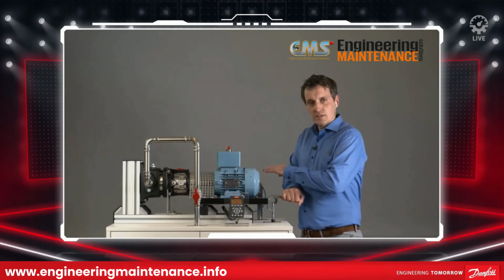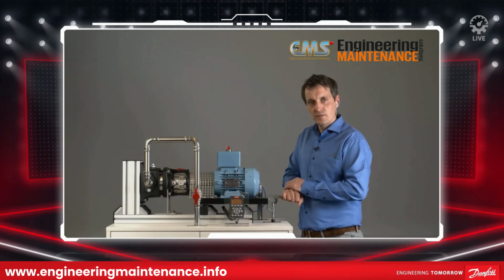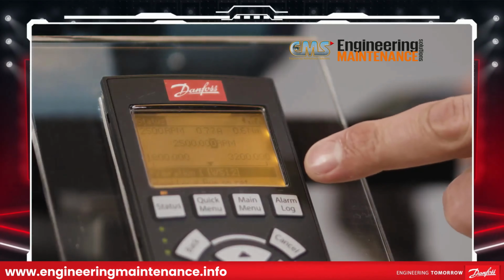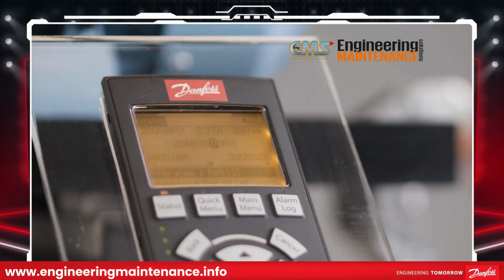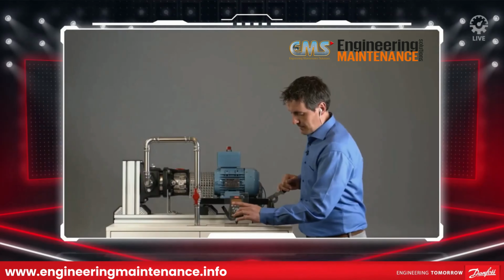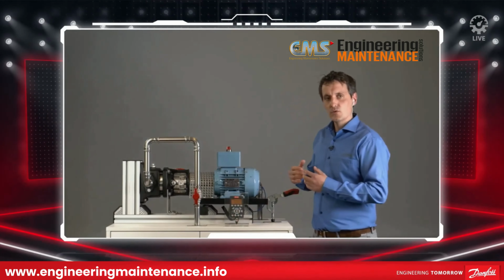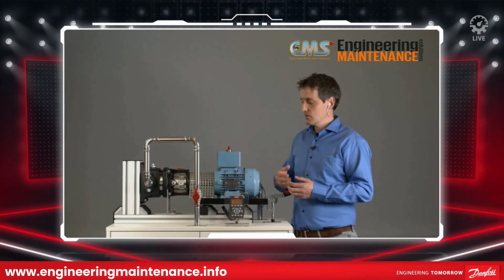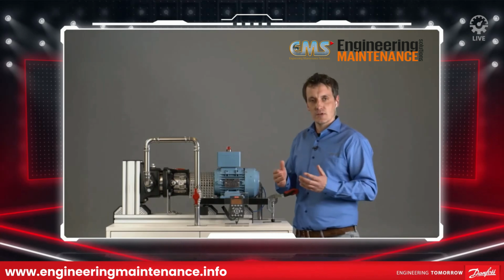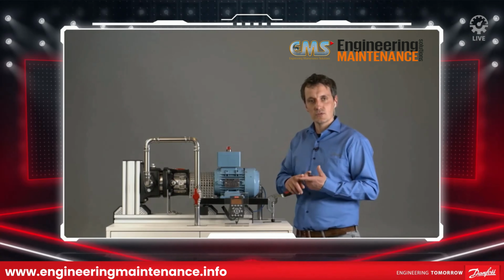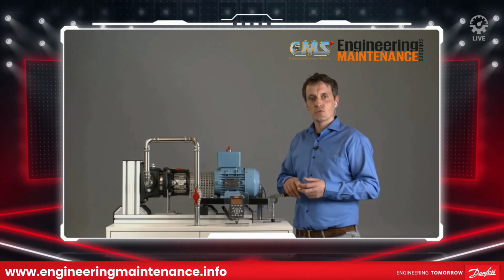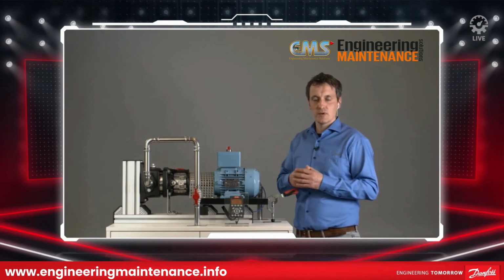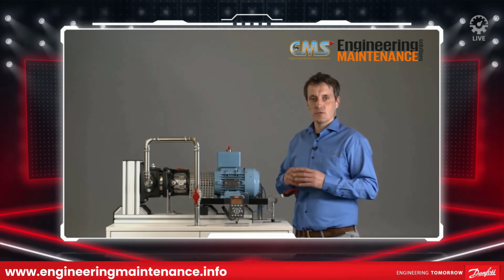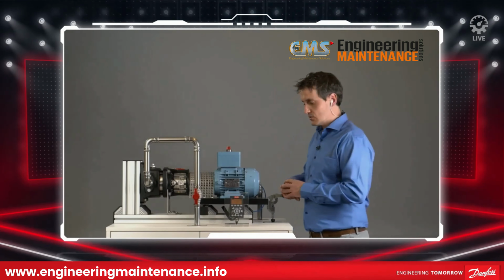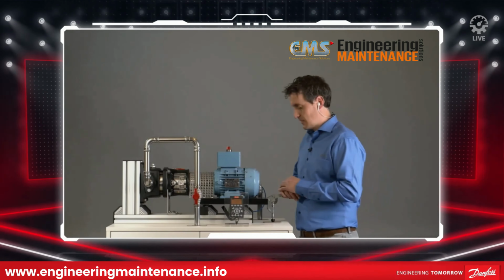And with the vibration sensor that is connected to the drive, the condition-based monitoring functionality inside the drive will actually notify us there's a high vibration. So with this notification, now you can start planning the maintenance. You can continue running, but you can start finding the right people, the right tools, the right spare parts. You can actually plan when to do it. Maybe you find a weekend where you can execute on it, or maybe you have production stops anyway. So this just allows you to plan maintenance.